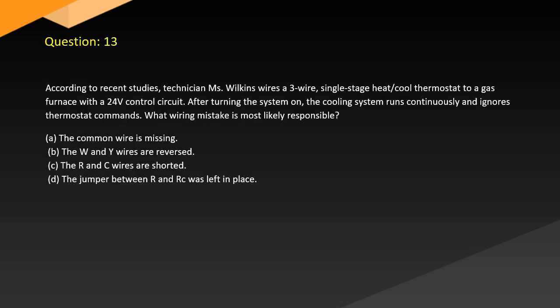Question 13. According to recent studies, Technician Wilkins wires a 3-wire, single-stage heat-cool thermostat to a gas furnace with a 24-volt control circuit. After turning the system on, the cooling system runs continuously and ignores thermostat commands. What wiring mistake is most likely responsible?